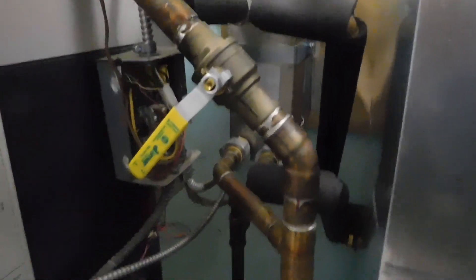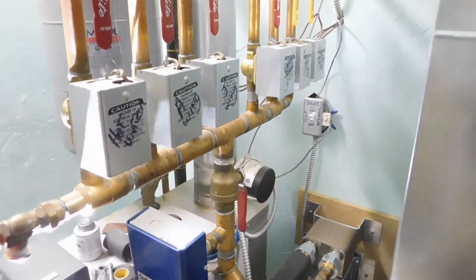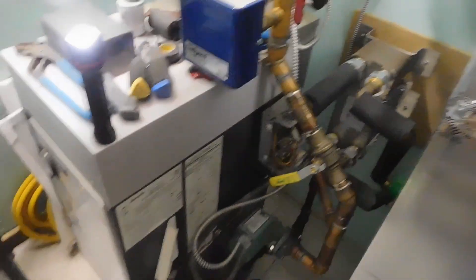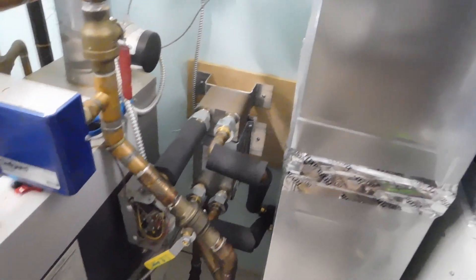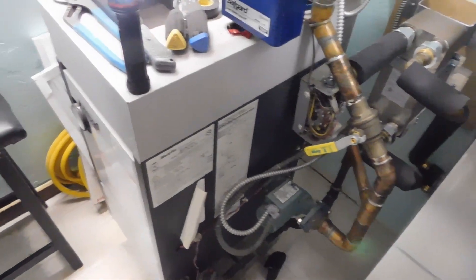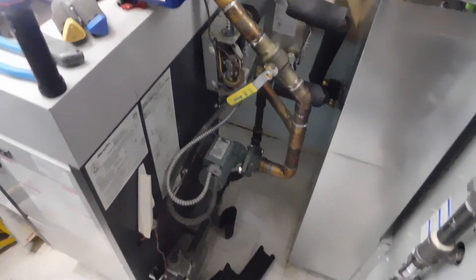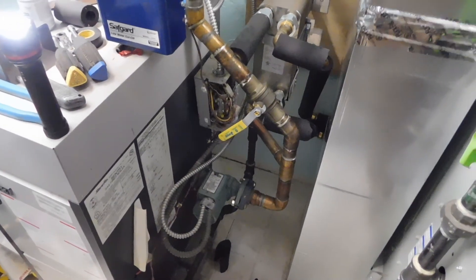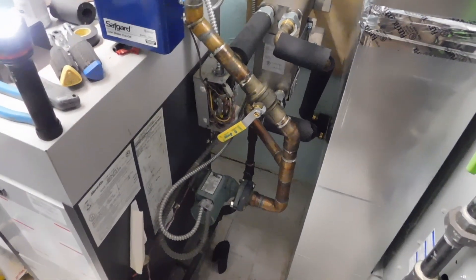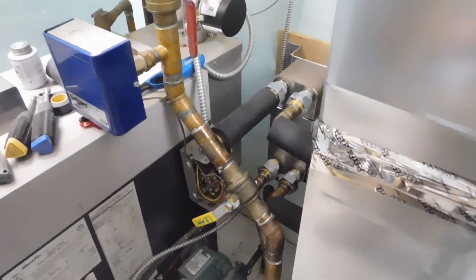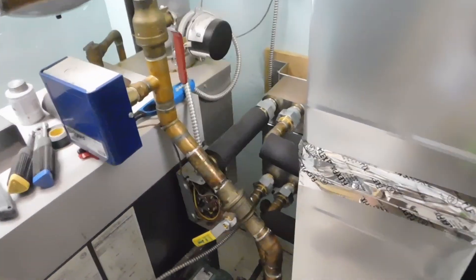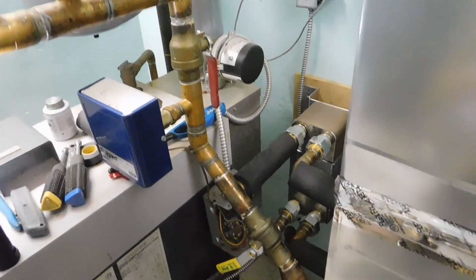I was afraid, or at least I wasn't sure whether or not I was going to be able to heat the water in the boiler without the pump running. You know, when the zones aren't on, nothing's moving. So I wasn't sure if the plate exchanger was going to be able to heat the water in the Slant/Fin boiler here, but it does. This thermal cycling, it actually heats it up fantastic.